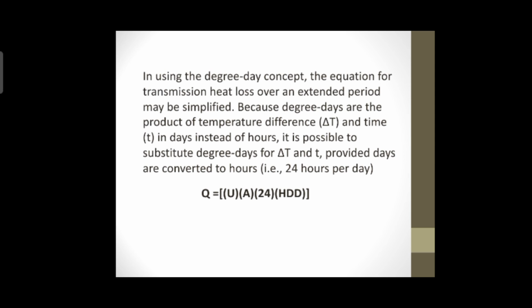where U is the overall coefficient of heat transfer in BTU per hour, degree Fahrenheit, square foot. A is the area of the assembly in square foot. 24 is an hour per day conversion. HDD is degree days in degree Fahrenheit. And Q is the quantity seasonal heat loss through the construction assembly in BTU. Similarly, the equation for air infiltration may be substituted with 24 hours a day and degree days to estimate the seasonal heat loss from infiltration.